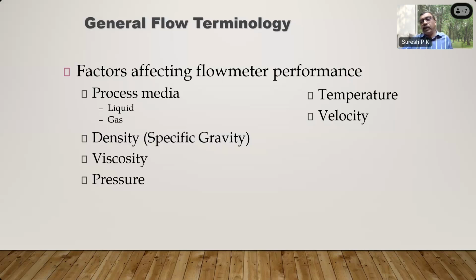It is an inherent characteristic of the positive displacement meter, because it takes out a certain volume from the flow intermittently and puts it back into the flow. There is a gap between the rotating element and the casing. The leak between the rotating element and the casing decides the error of the meter. The leak can increase if your viscosity is low. The leak will decrease if the viscosity is high, because the thickness of the liquid sticking to the wall of the stator will be more, so the gap between the stator and the rotor will be less.